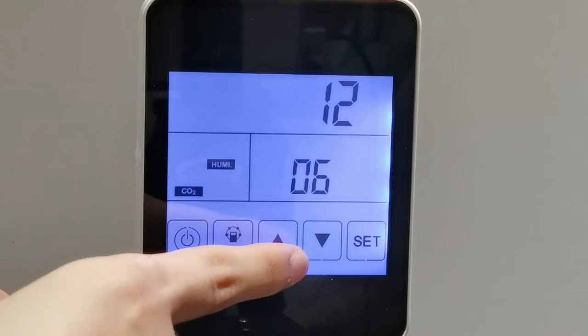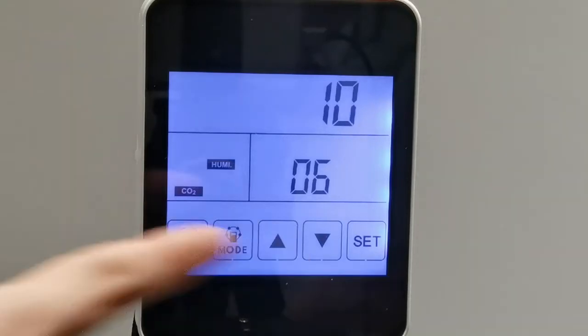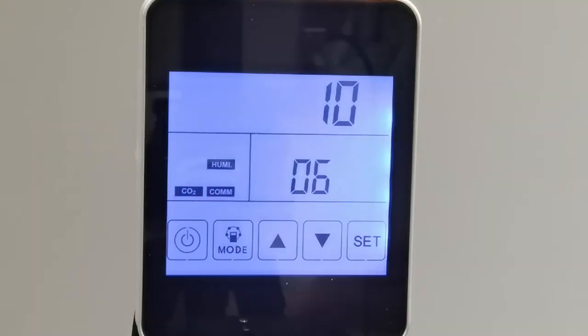Okay, good. With the above default parameters 04 to 06, the defrosting logic is: when the exhaust air side of the heat exchanger temperature is lower than -1 Celsius degree and lasts for 1 minute, and the interval of defrosting is longer than 30 minutes, the exhaust fan will run at highest speed automatically for defrosting, and the supply fan will stop until the exhaust air side temperature is higher than 15 Celsius degrees for 1 minute, or the defrosting time is longer than 10 minutes.